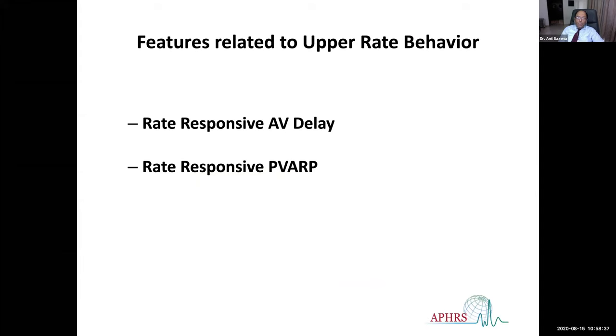This was a young man, 16 or 17 years old, so we need to program the upper rate to about 150, 160, 170. But at nominal settings of AV delay and PVARP, that may not be possible, because these consume time in the cardiac cycle. AV delay is about 150 to 200 milliseconds, and if we program the PVARP to about 250 to 300, the total may become around 500, which limits the upper tracking rate to 120.